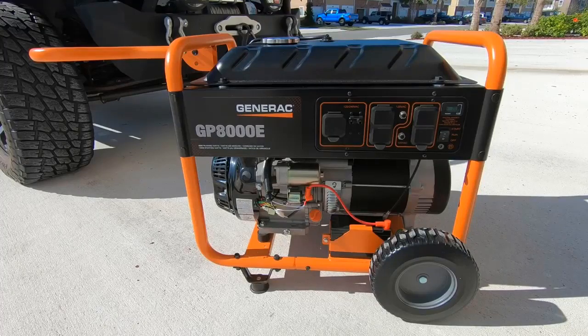I filled it with the supplied oil, put in a couple of gallons of rec fuel, pushed the button and it fired right up. I plugged a couple of fans into the 120V receptacles and ran it for 30 minutes with the light load on it. I'm having a manual transfer switch put in and will test under a real load after that.